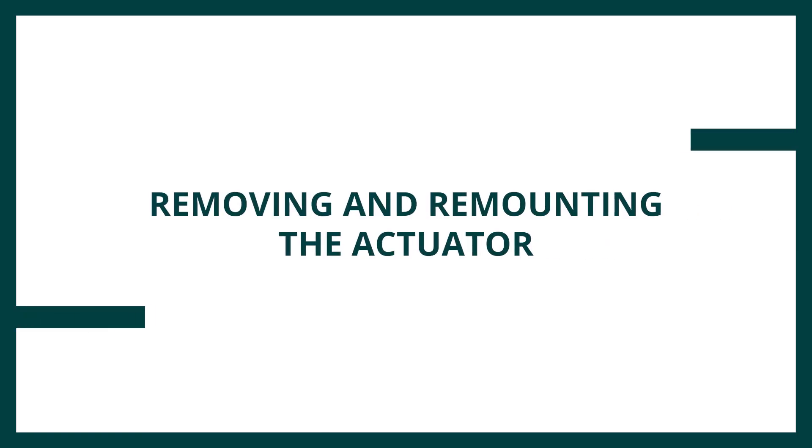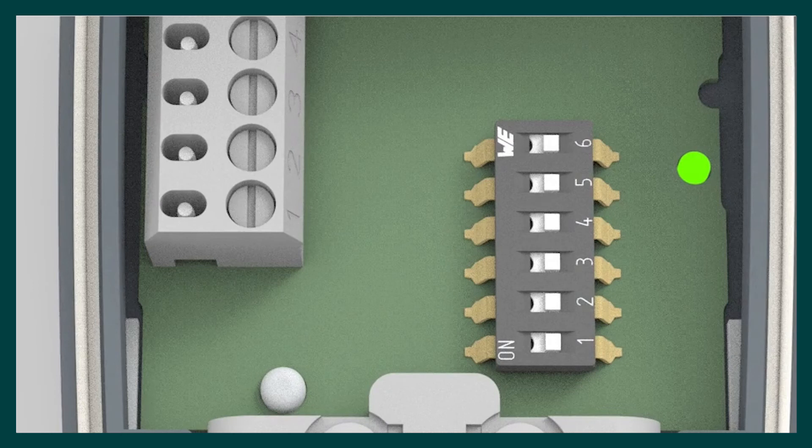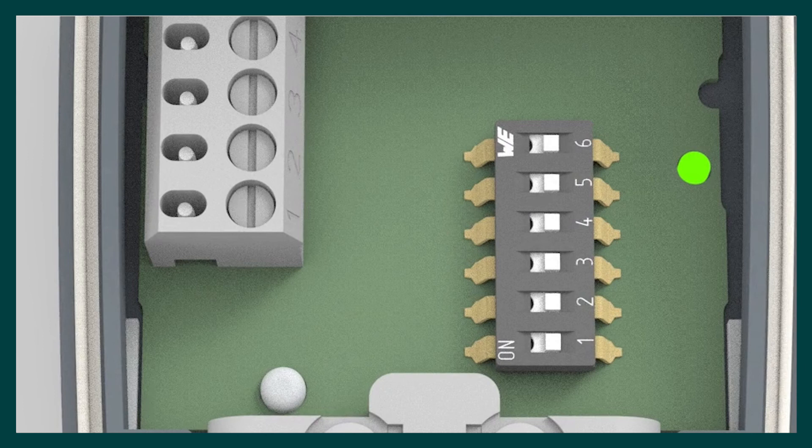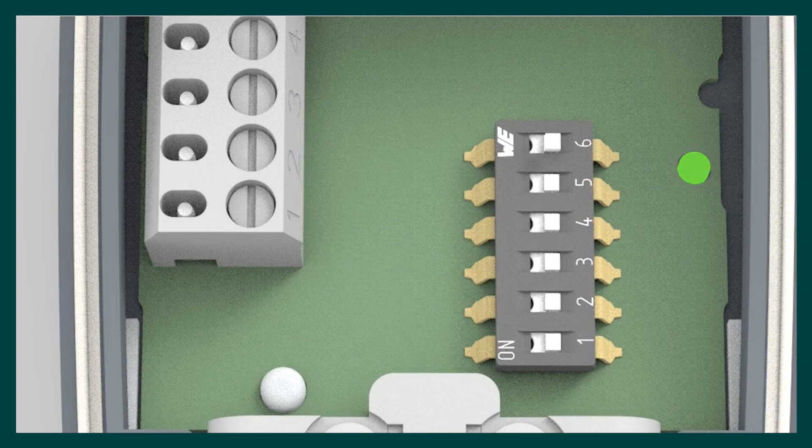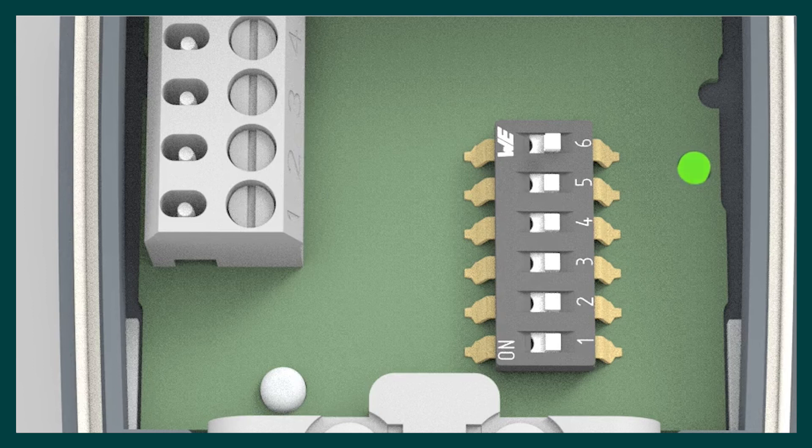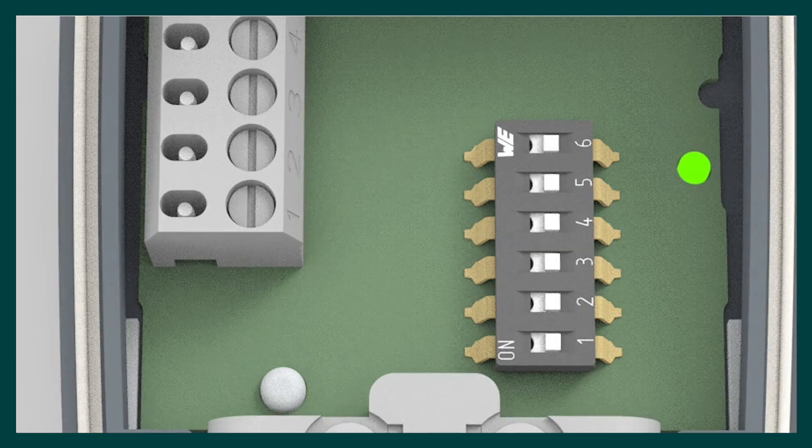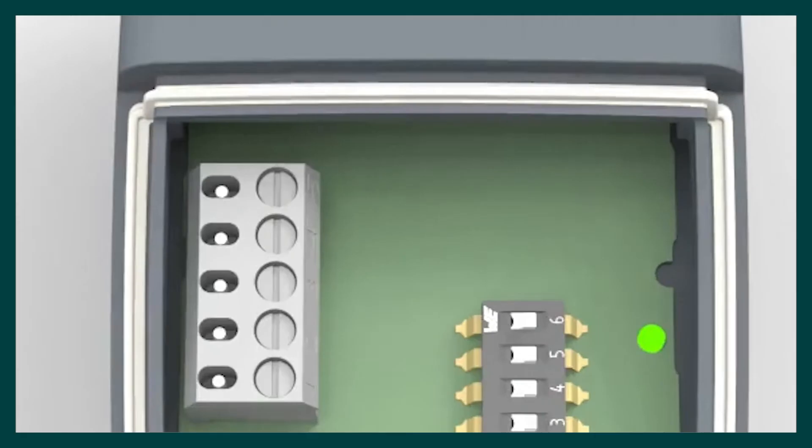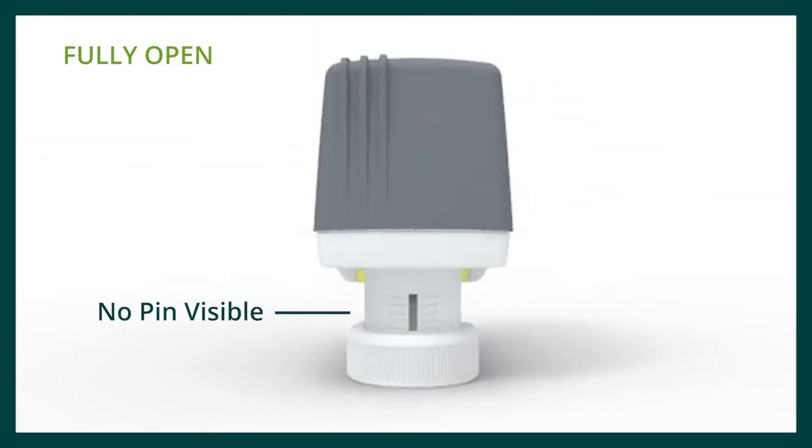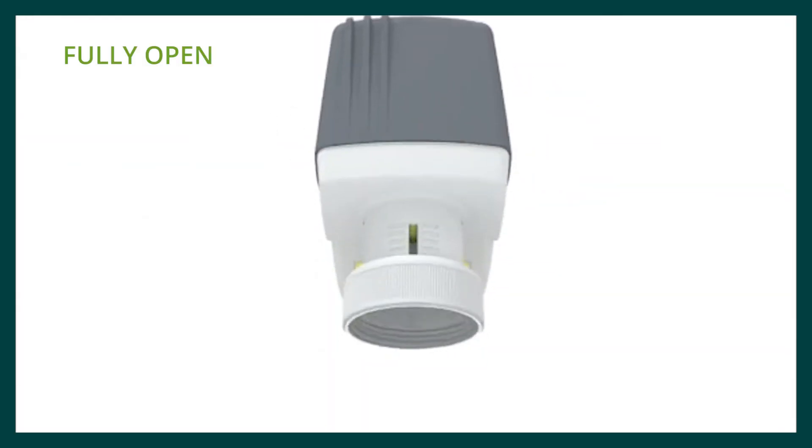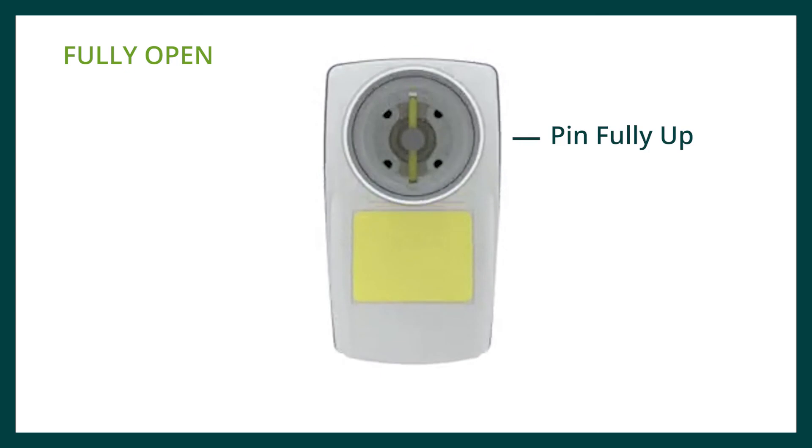Only remove the actuator from the valve in the fully open position. Drive the actuator open with the control signal or by flipping DIP switch 6 to the ON position. Once fully open, turn the power OFF. DIP switch 6 should be reset to the OFF position and should remain in this position whilst the actuator is not fitted to the PICV. Only remount the actuator onto the PICV in the fully open position. Once remounted, turn the power ON. The actuator will recalibrate to the PICV.